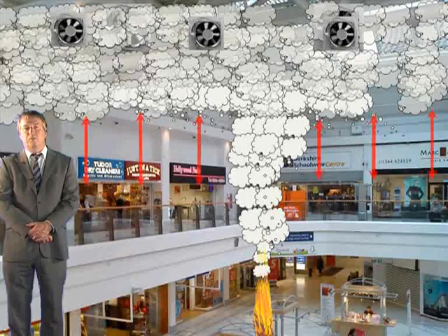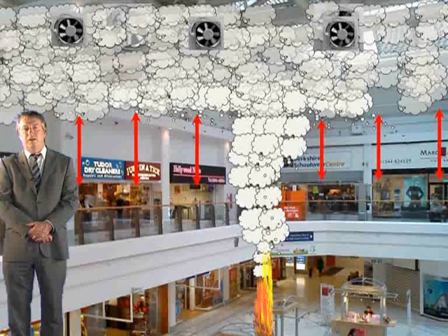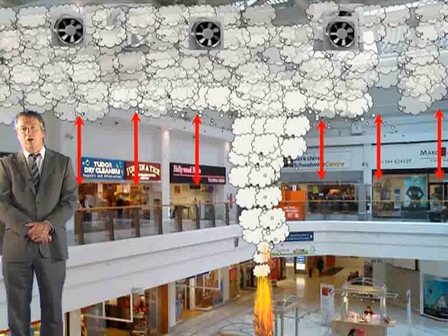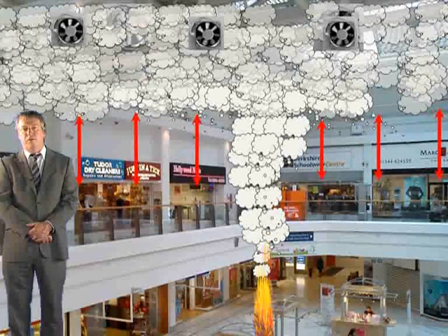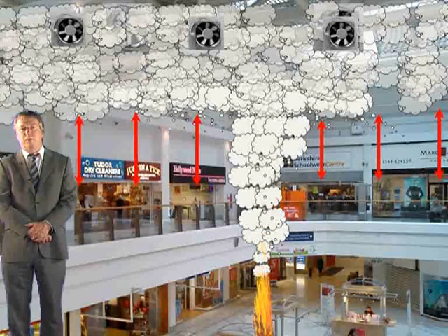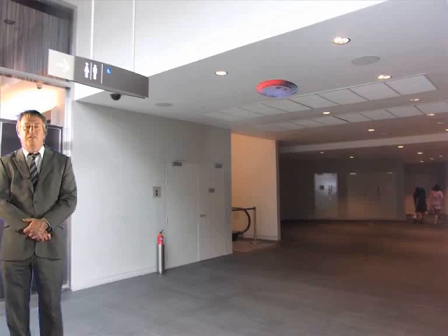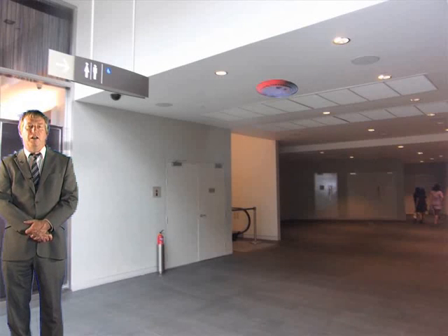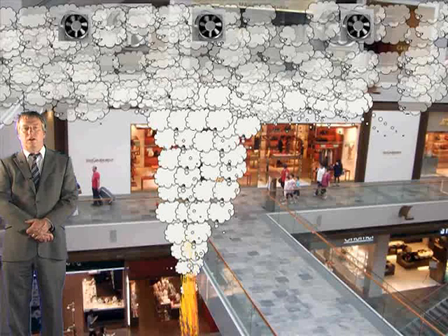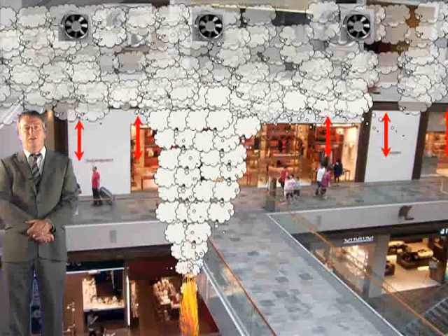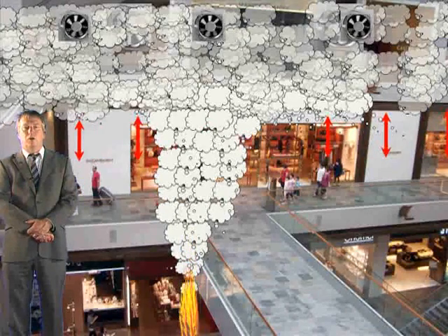The thermally buoyant smoke forms a layer beneath the ceiling. The smoke extraction required is calculated to be large enough to keep the smoke at a safe height above the heads of people long enough for them to make their safe escape. It is essential that the system comes into operation as early as possible during the fire, and it is usual to initiate operation automatically on receipt of a signal from a smoke detection system. Limiting the accumulation of smoke means that the base of the smoke layer can be controlled.